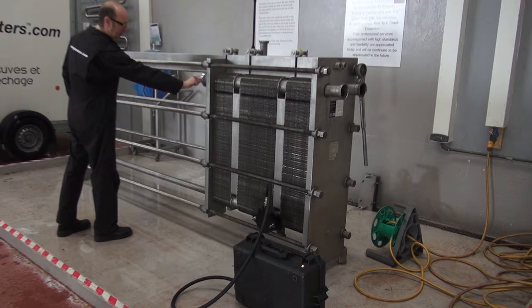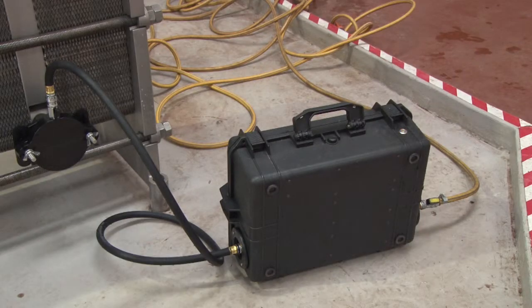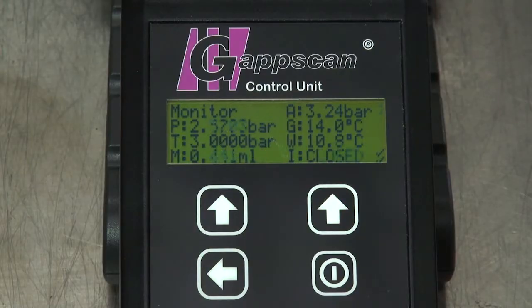The pressure will start to build in the exchanger until it reaches the target pressure. The internal valve may be heard modulating the input supply. On the control unit, you will see the live variable pressure P increasing to the default target pressure T of 3 bar. When P and T have stabilised to within 2 decimal places, you are ready to start the test. If P does not stabilise, it usually means there is air in the system, so you would have to bleed more water through and start again.